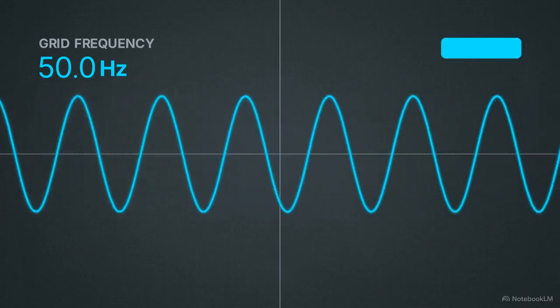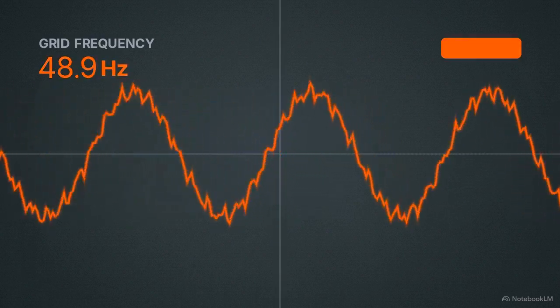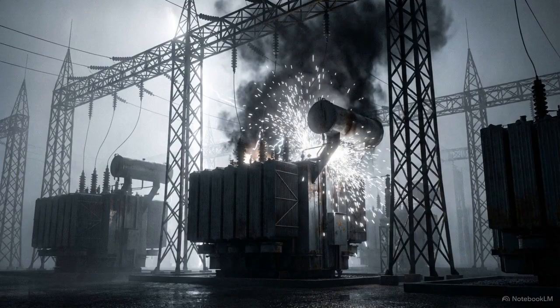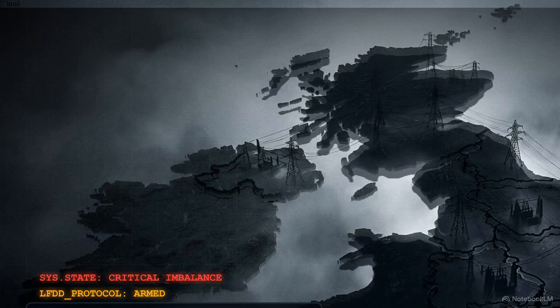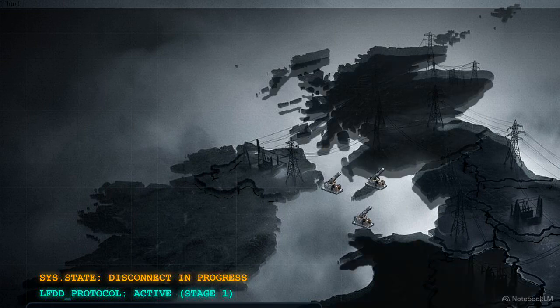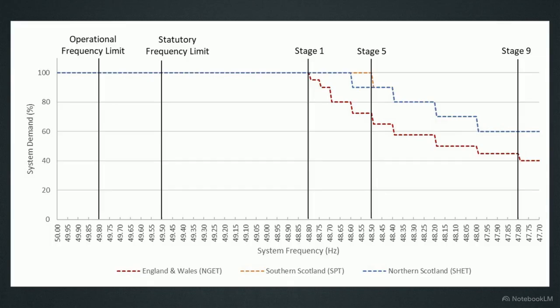With supply plummeting, the frequency of the alternating current in the grid went into freefall. If it drops too far, the entire national network enters a death spiral, causing severe physical damage to power stations and a total system collapse. To prevent total failure, the grid relies on a last resort protocol called Low Frequency Demand Disconnection, or LFDD. LFDD is an automated mechanism that intentionally cuts off power to entire regions to force supply and demand back into balance. This chart shows the program's trigger thresholds for demand disconnection.